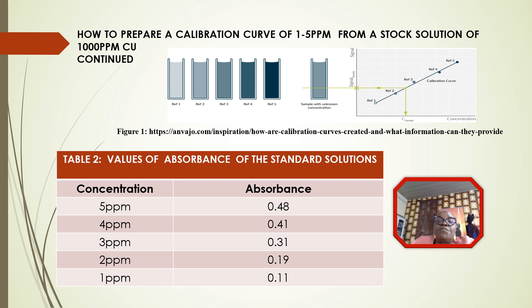If the concentration of your unknown sample is not within the calibration curve range, what you do is either redilute and recalibrate, or concentrate and recalibrate, until you get your sample within your curve. You don't assume that by extending the curve you will get your sample. It is very important that the absorbance of your unknown sample falls within your calibrated range.